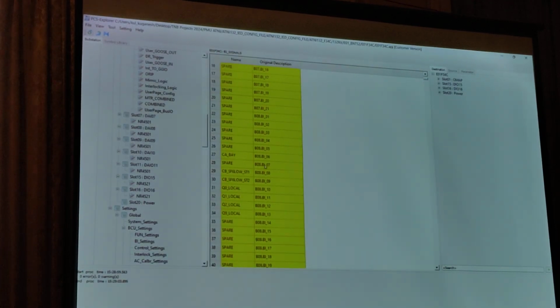If you are copying another bay, and then try to make the signals follow the same BI numbers, cut numbers in the drawing lah. I mean, future whoever doing the drawing, let's say it's a new bay and new vendor is doing the drawing, if possible try to follow the similar base signal positions lah. Or position or the signal follow the product app also is good enough, because when you try to do some changes, you won't have major changes to troubleshoot as long as you follow the previous pattern.